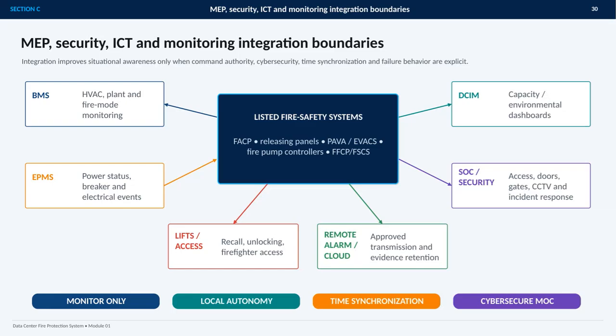This section focuses on the integration boundaries between fire protection, MEP, security, ICT, and monitoring systems. The central point is that integration improves situational awareness only when responsibilities and operating rules are clearly defined. Integration must not replace local fire system authority or autonomy. The listed fire safety systems, including the fire alarm control panel, releasing panels, voice evacuation, fire pump controllers, and firefighter control systems, remain the primary safety functions. Other platforms provide supporting information.